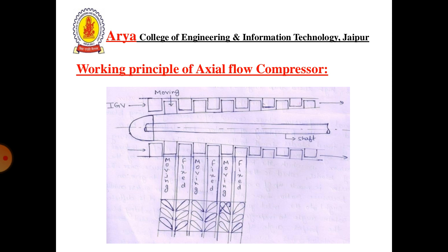Working principle of Axial Flow Compressor: the working fluid enters and leaves the compressor in the axial direction. It is a rotating airflow-based compressor in which the working fluid principally flows parallel to the axis of rotation. The kinetic energy is transmitted to the air by rotating blades, which is then converted into pressurized flow. The compressor is made of a number of stages to give an overall pressure ratio from inlet to outlet.